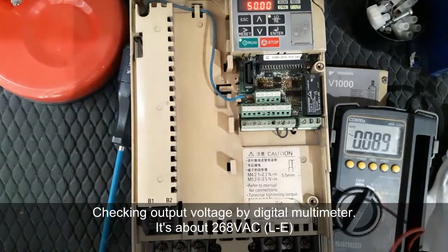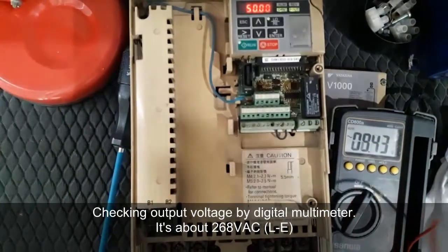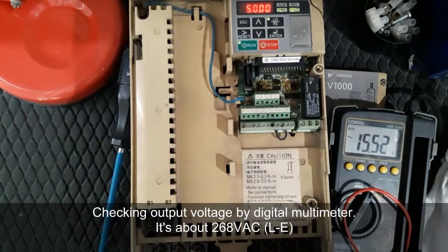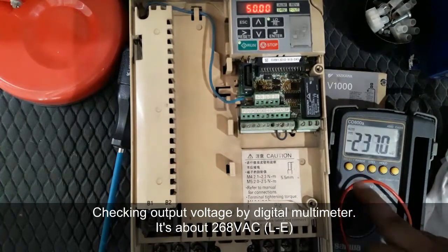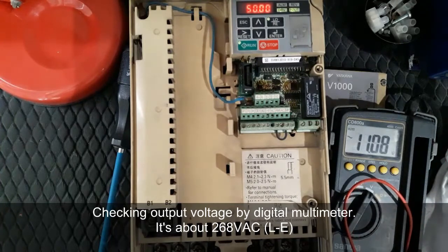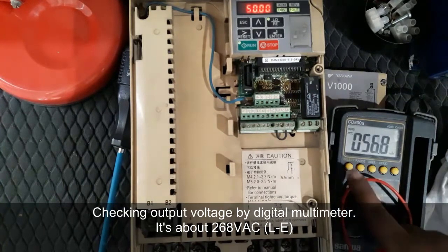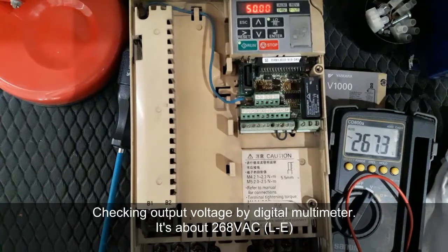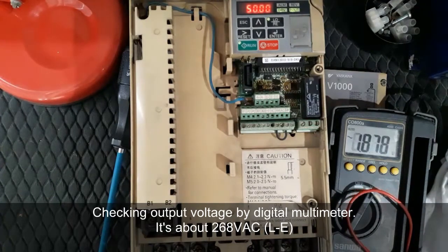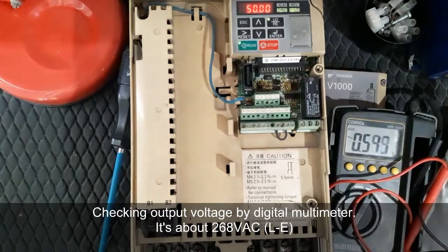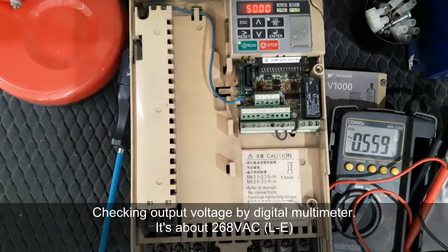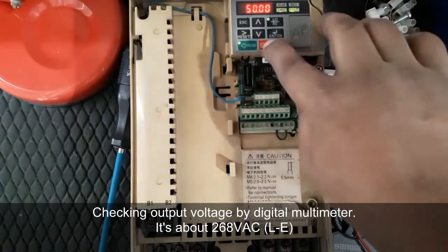Here we found about 268 volt AC at 50 Hz frequency. So here we are checking U, V, W and we found about 268 volt AC on the output terminal of this inverter. We tested the output voltage. Now power off the inverter.